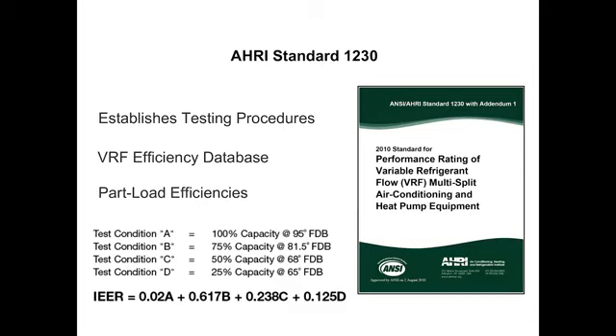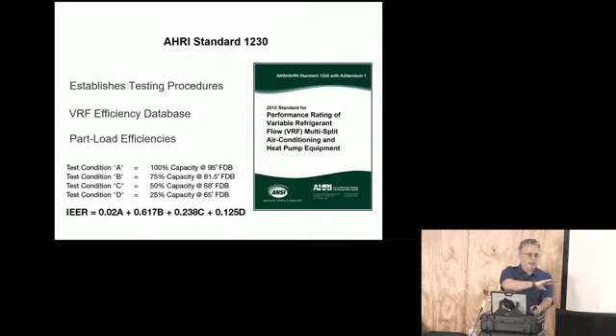So in terms of the SEER rating, for a commercial VRF it is AHRI standard 1230. And it takes these conditions here and averages them. And this is supposed to be a swath between all like 4 different climates. So they're doing their best, but it tells a little better story than SEER rating, but it doesn't tell the whole story.